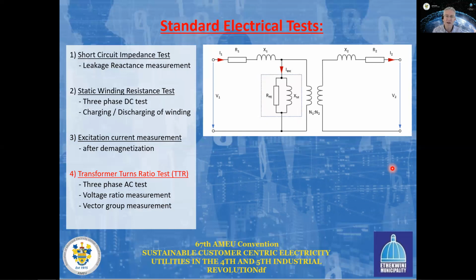But the other big advantage about this 3-phase AC test is that we can energize our transformer with a balanced AC voltage. We will then not only measure the ratio for each phase, but also the phase angle shift between the HV and the LV, the vector group measurement of that transformer. And we're then characterizing this ideal transformer that we see in the middle here, this ideal transformation ratio.